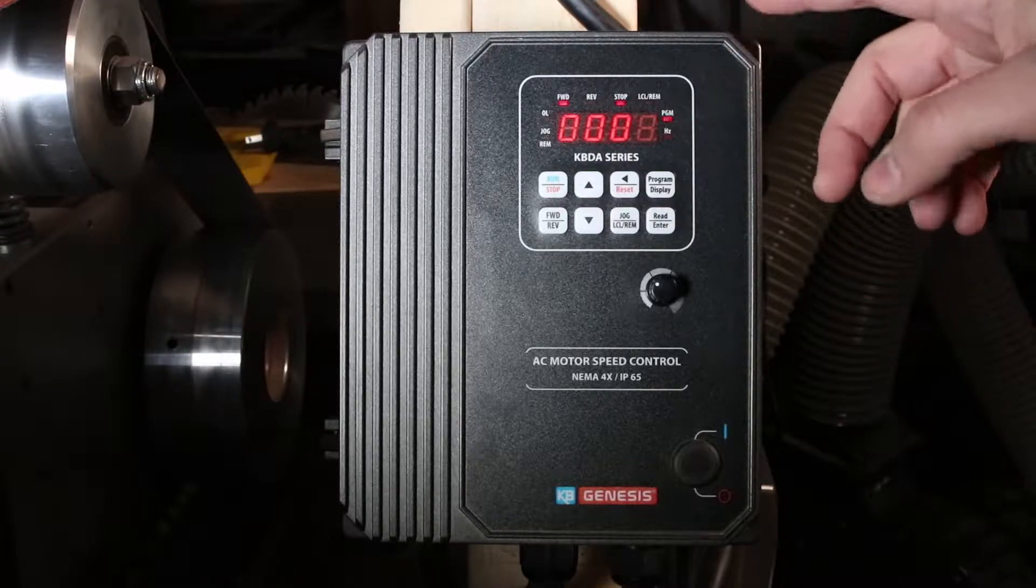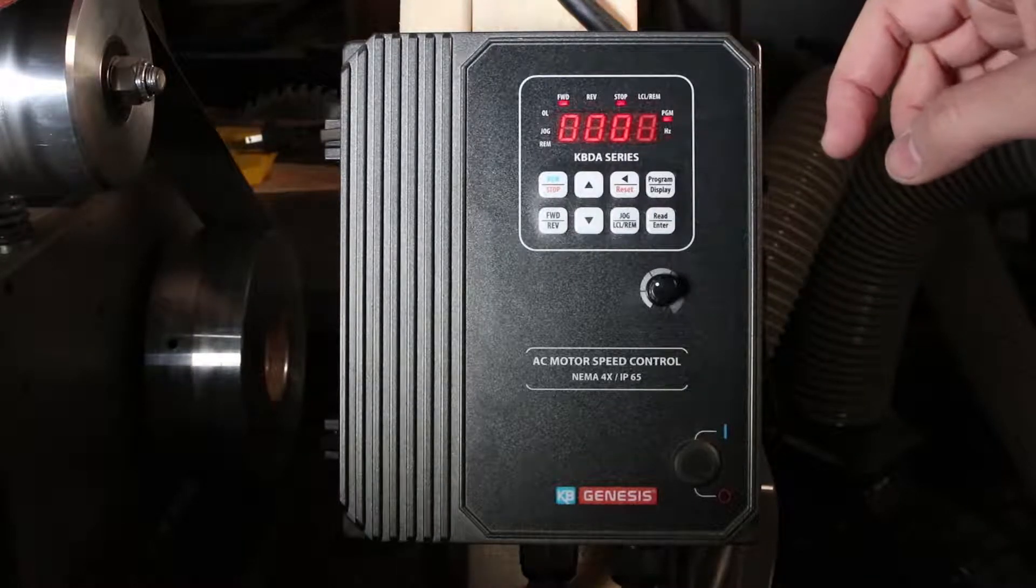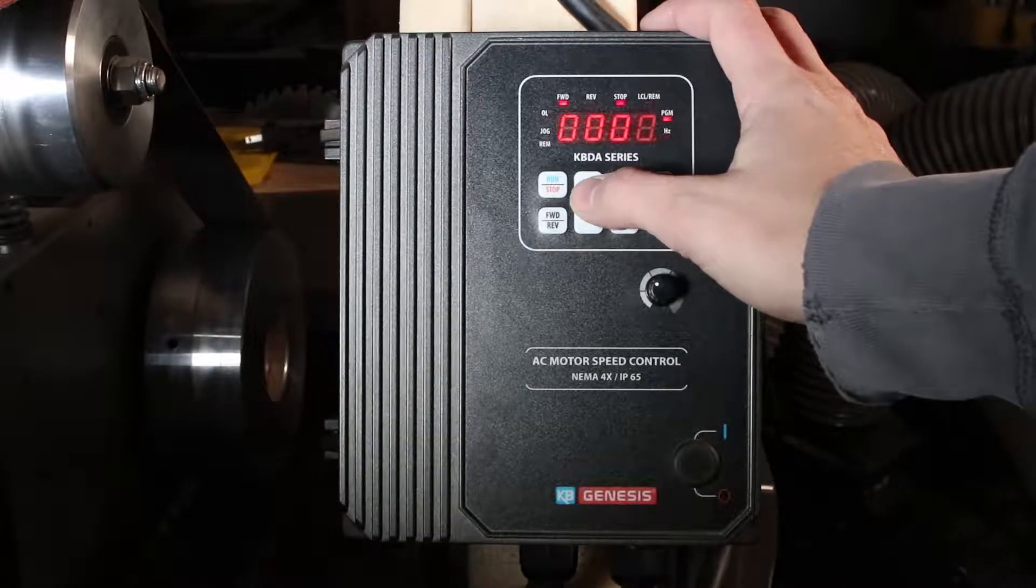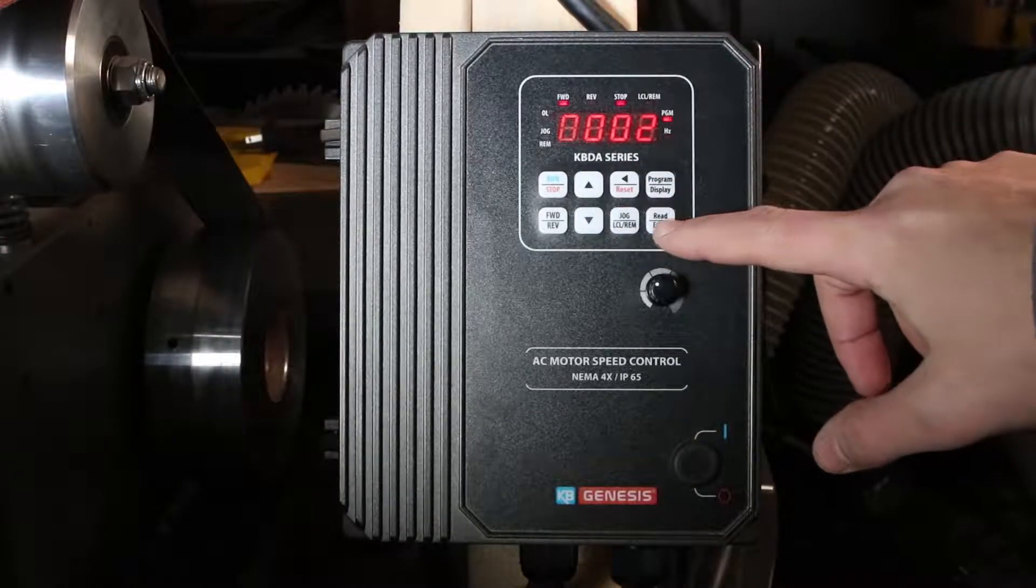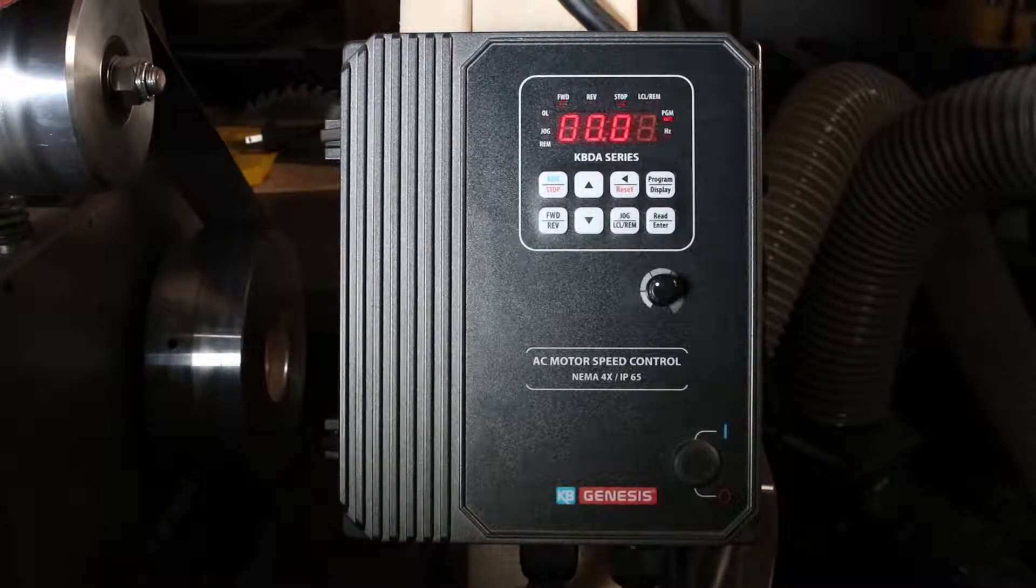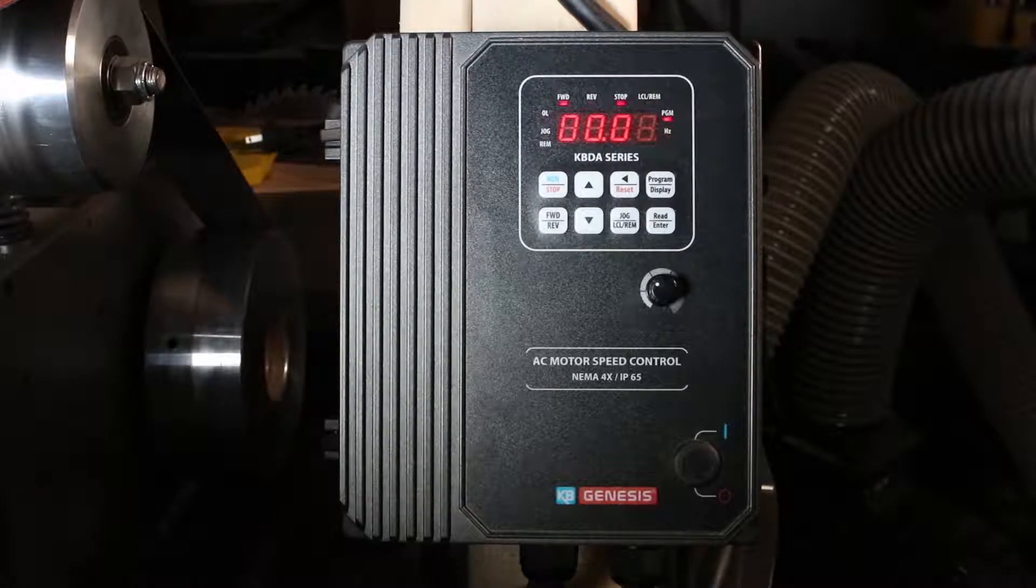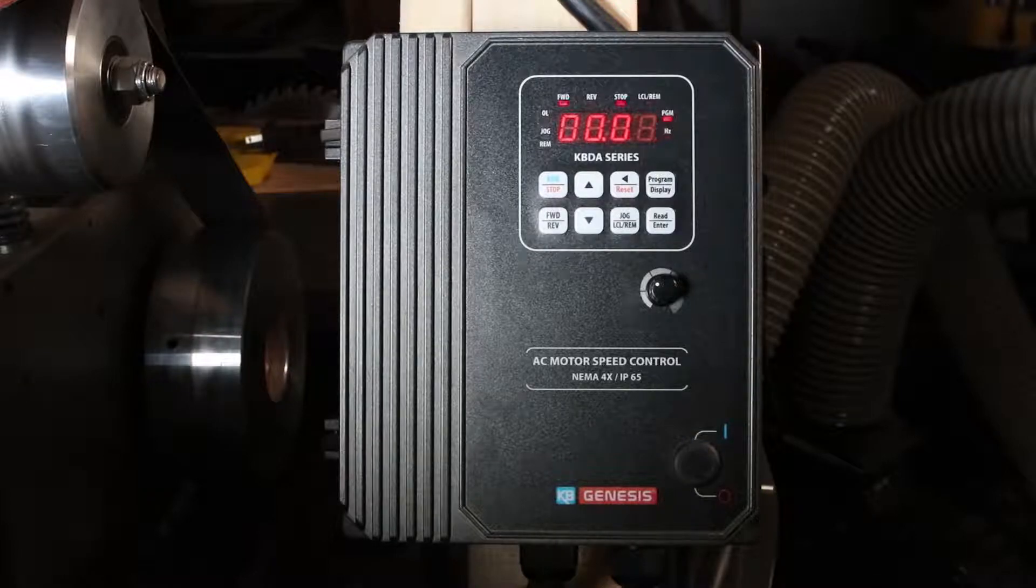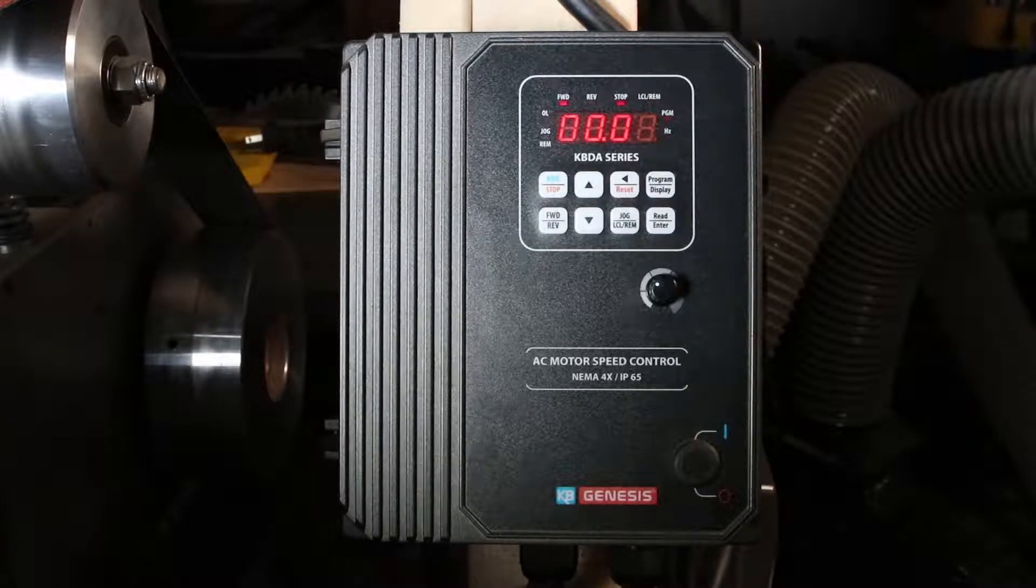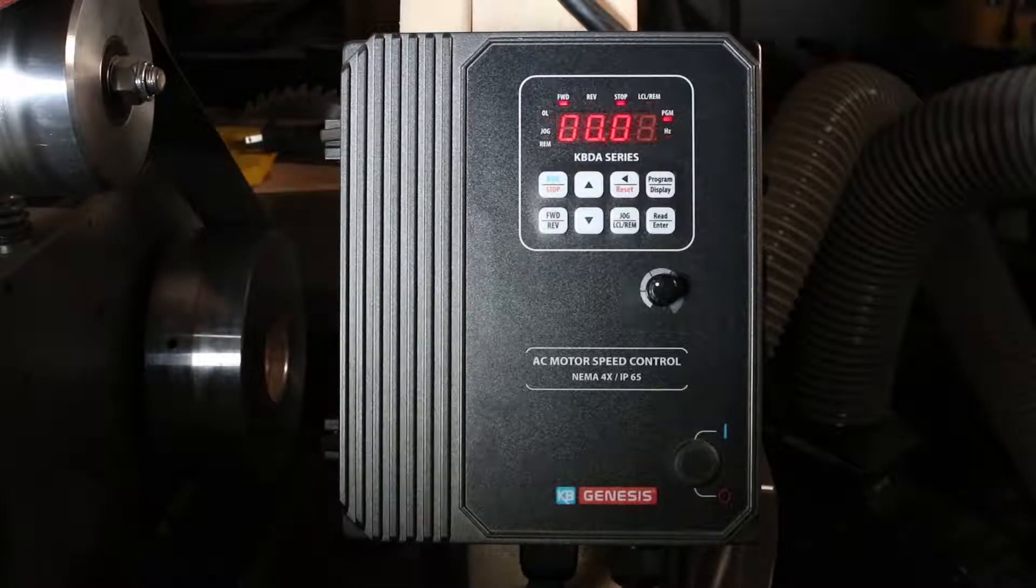Now standard is 60 Hertz. If you change it to one, it'll be 50 Hertz, and then you want to go to custom, which would be 2. Now the VFD knows that you have a custom motor, or at least that's what it believes.